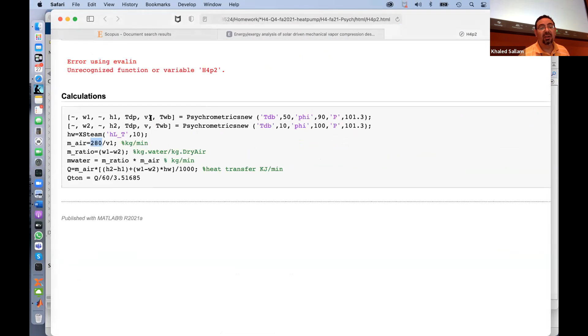When it comes to how much is the refrigeration capacity, that is the first law. Q is M air times H2 minus H1, plus how much water is leaving. So basically what we're saying is that the cooling that happened to the air is absorbed in two ways: water and refrigeration. The water that condensed, that exits, and refrigeration.